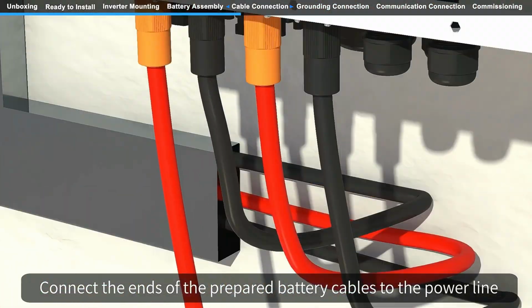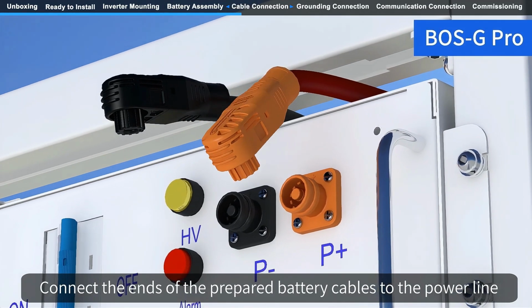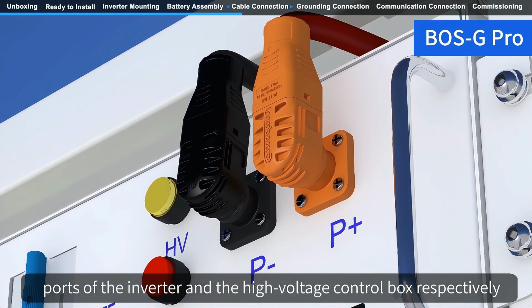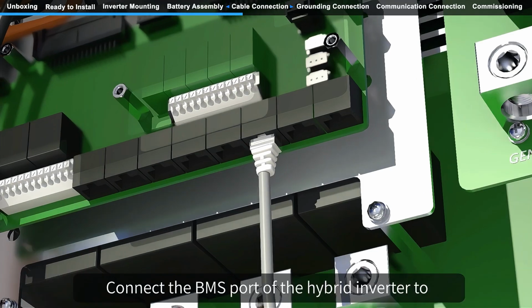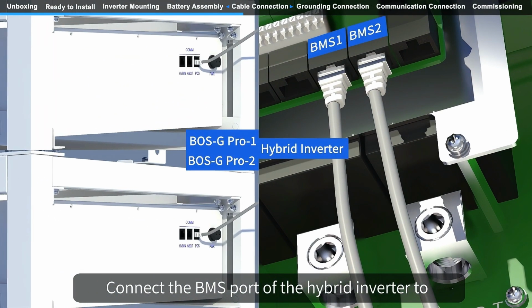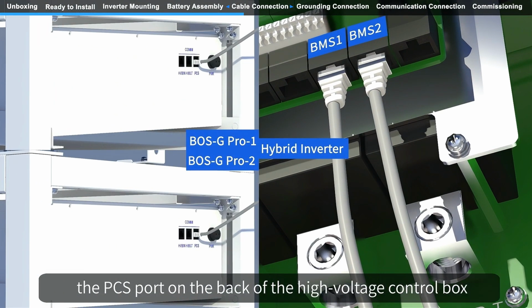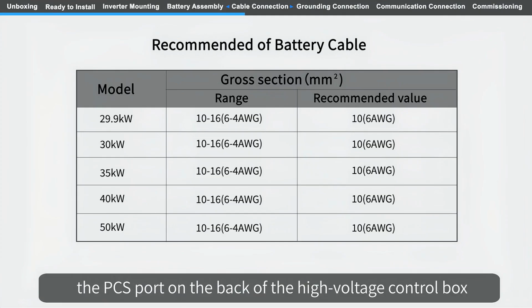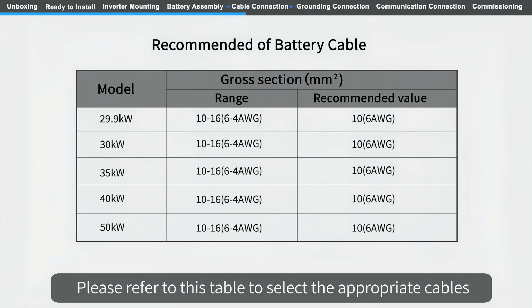Connect the ends of the prepared battery cables to the power line ports of the inverter and the high voltage control box, respectively. Connect the BMS port of the hybrid inverter to the PCS port on the back of the high voltage control box. Please refer to this table to select the appropriate cables.